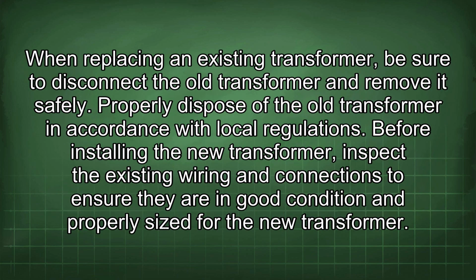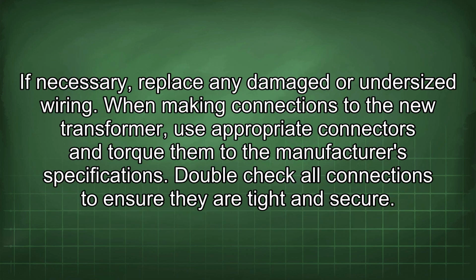When replacing an existing transformer, be sure to disconnect the old transformer and remove it safely. Properly dispose of the old transformer in accordance with local regulations. Before installing the new transformer, inspect the existing wiring and connections to ensure they are in good condition and properly sized for the new transformer.